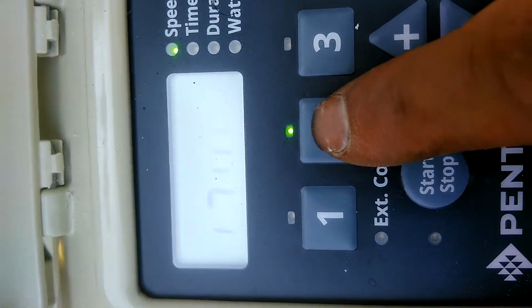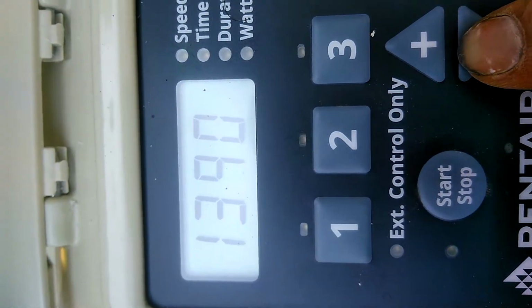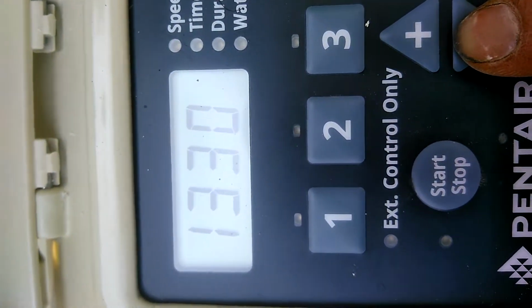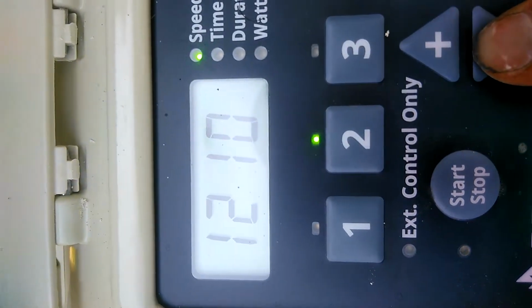So to let the pump have a break, what we're going to do is go on the speed 2. Now it's asking me what speed I want for speed 2. So I actually want the pump to be off on speed 2. So what I'm going to do is go down here and change that 1400 to 0 RPMs. Okay?